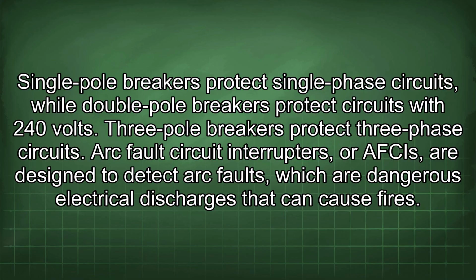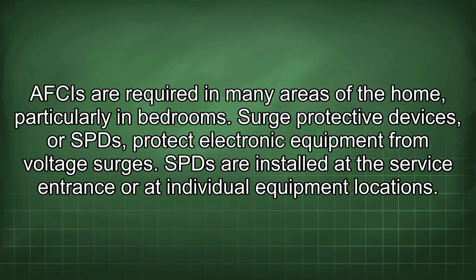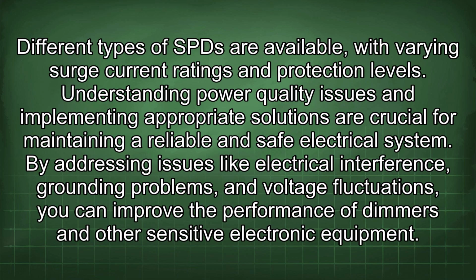Arc fault circuit interrupters, or AFCIs, are designed to detect arc faults, which are dangerous electrical discharges that can cause fires. AFCIs are required in many areas of the home, particularly in bedrooms. Surge protective devices, or SPDs, protect electronic equipment from voltage surges. SPDs are installed at the service entrance or at individual equipment locations. Different types of SPD are available, with varying surge current ratings and protection levels. Understanding power quality issues and implementing appropriate solutions are crucial for maintaining a reliable and safe electrical system.